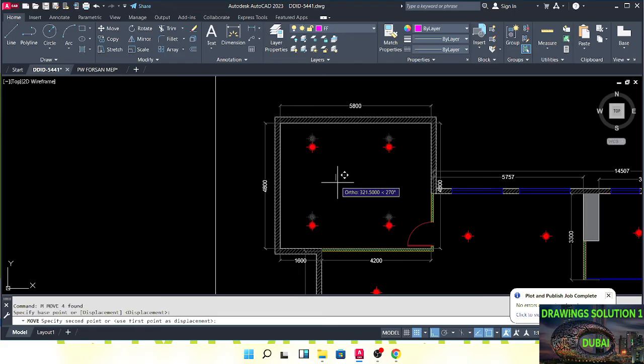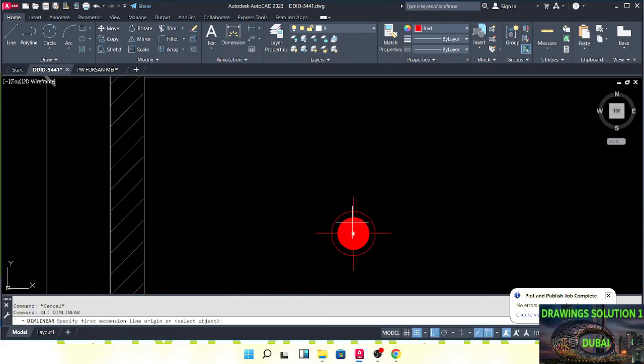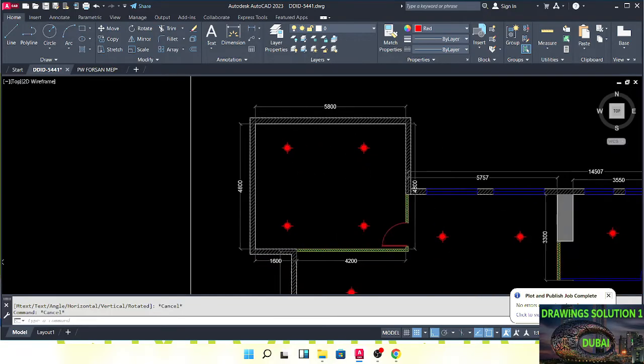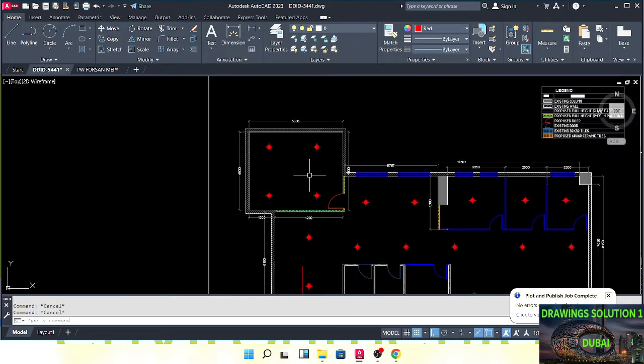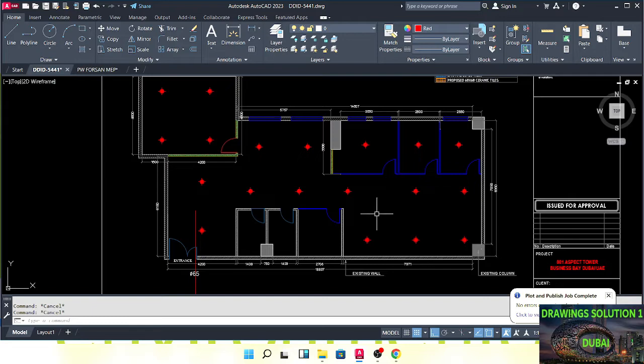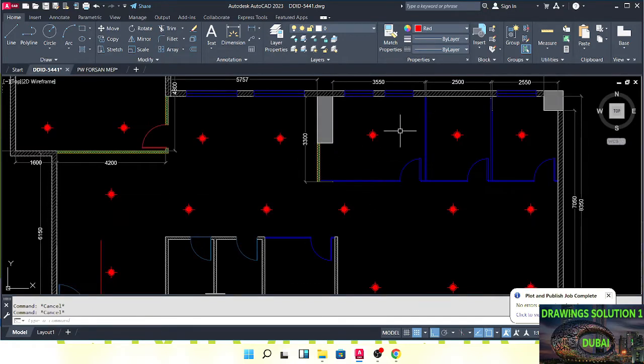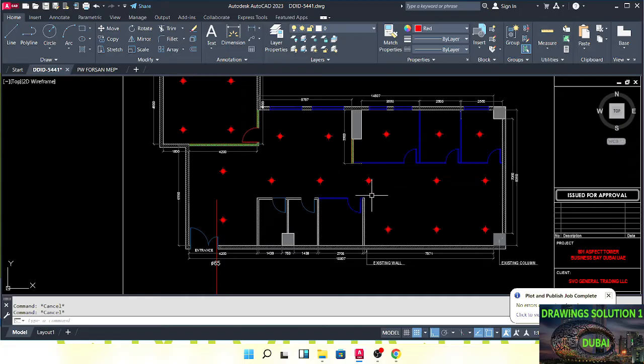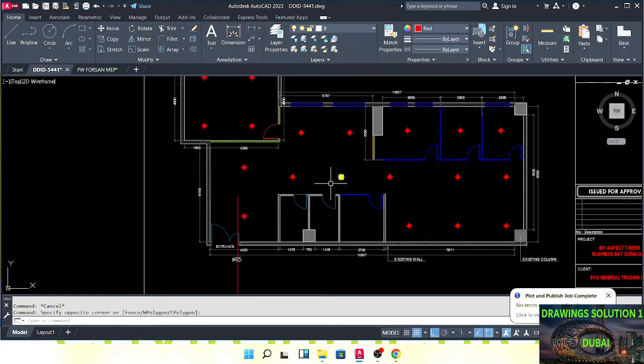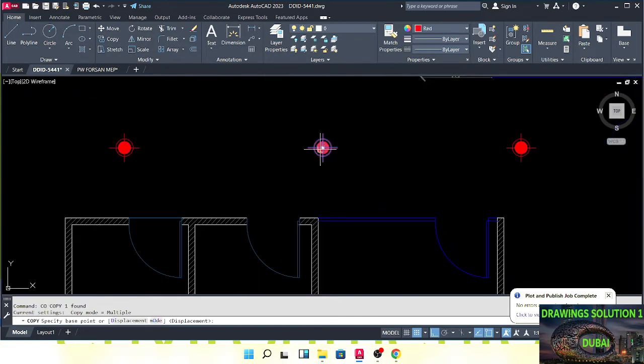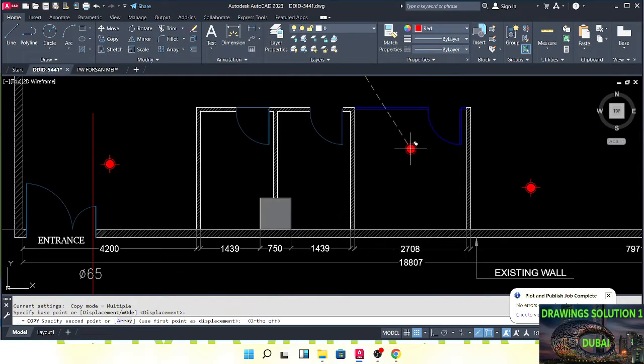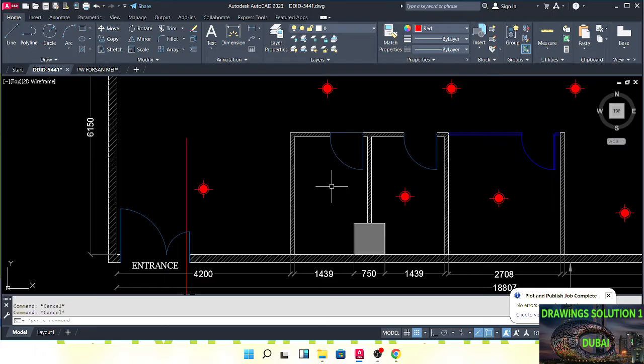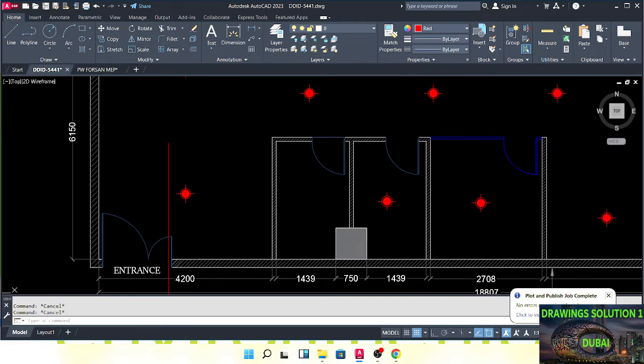Shift it down and check the distance from here — it should not be less than 50 centimeters. 90 is too much, this is enough now. This is done, this is done, this is done. Here we can keep two sprinklers but let's keep one only — if they comment we will see later. In this office we can make one sprinkler.